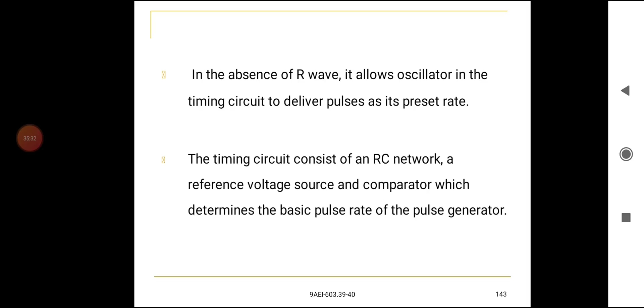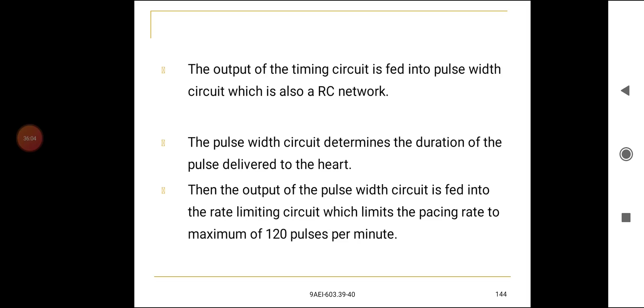The timing circuit consists of an RC network, a reference voltage source, and a comparator, which determine the basic pulse rate of the pulse generator. The output of the timing circuit is fed into the pulse width circuit, which is also an RC network. The pulse width circuit determines the duration of the pulse delivered to the heart. Then the output of the pulse width circuit is fed into the rate limiting circuit, which limits the pacing rate to a maximum of 120 pulses per minute. The output circuit provides a proper pulse to stimulate the heart. Thus, the timing circuit, pulse width circuit, rate limiting circuit, and output circuit are used to produce the desired pacemaker pulses to pace the heart.